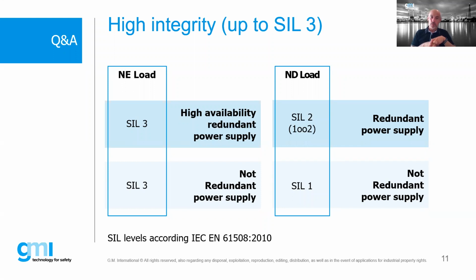HFT is zero if you use just one power supply. Why? If you use a redundant power supply, the SIL level remains SIL 3. You don't increase it. That is the very highest in the industry requirements.